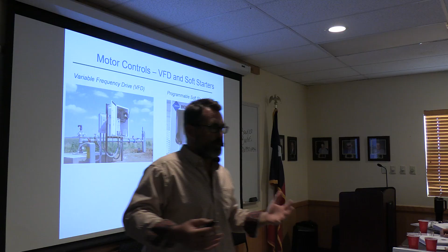I think even side-by-side horsepower per horsepower, this is how this industry has changed. You probably can get a less expensive drive in a panel than you can an equivalent soft starter in the panel. At least the retailers that I've been working with, drives are on the table up to 100 horsepower just ready to go, where the soft starts have to get ordered in. That's how the industry has changed in that way. May not be the same here. It's been a long time since I've priced the drive here.